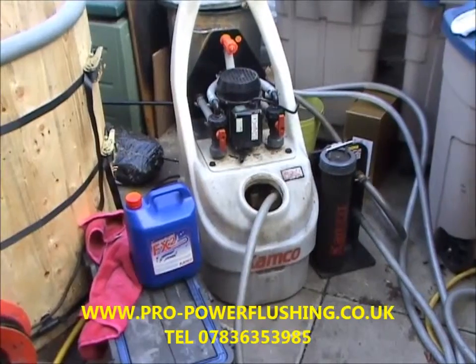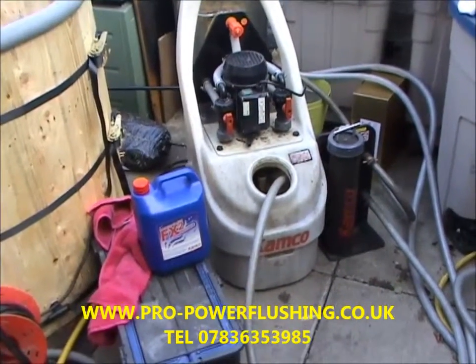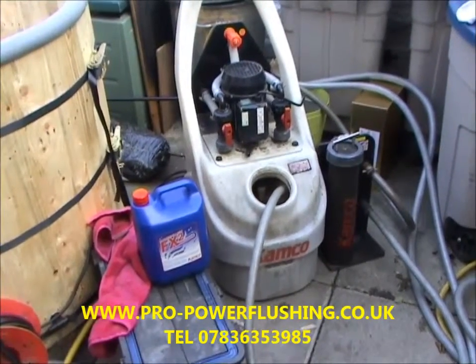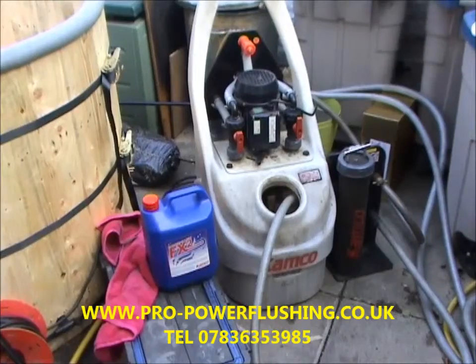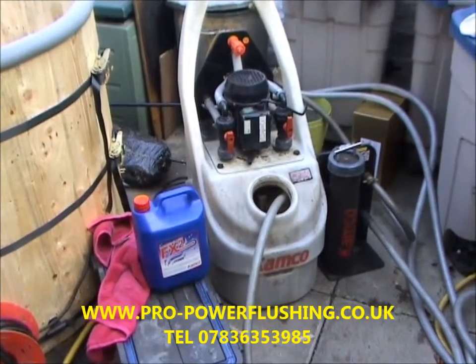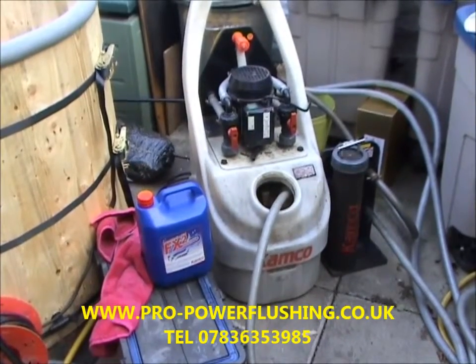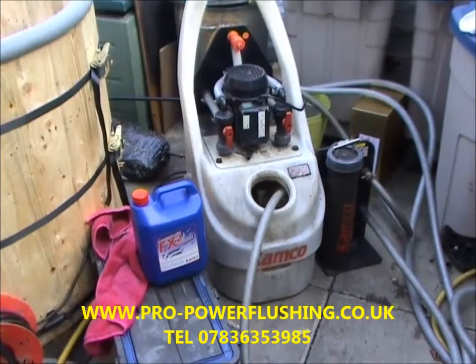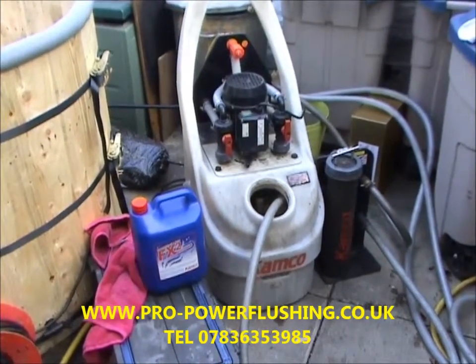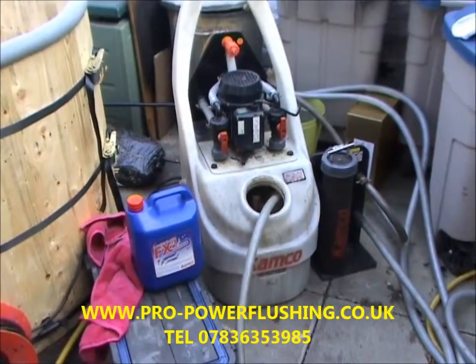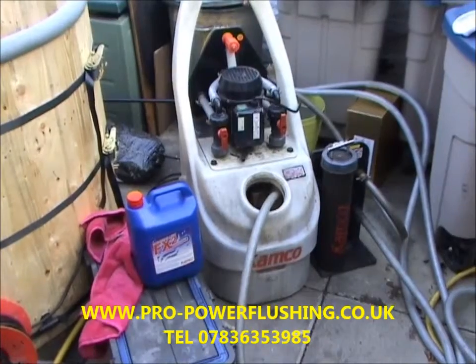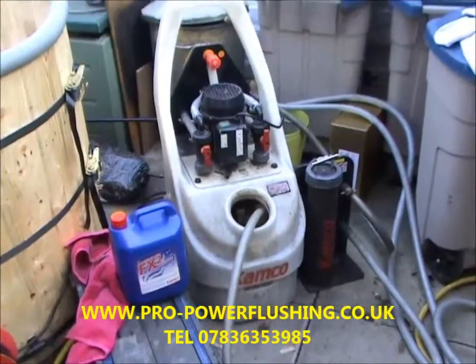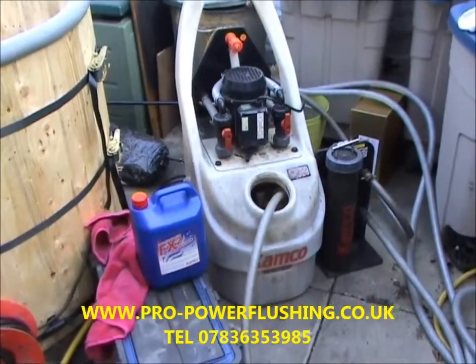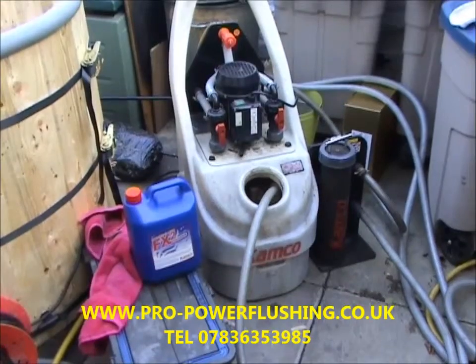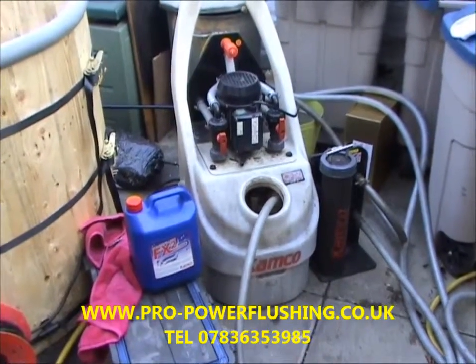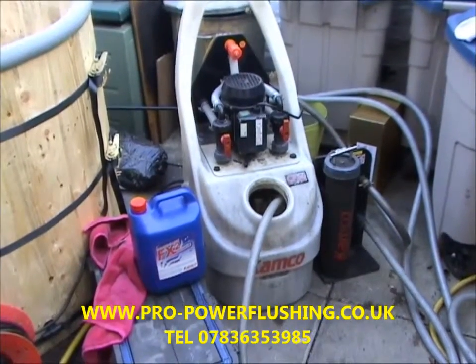We've done a system a few weeks back, and the system needed a power flush. It was a Worcester Bosch boiler, and the heat exchanger had cracked, and I think it was British Gas who were covering the system, but they basically said it needs a power flush before we're going to put a new heat exchanger in. So we went and power flushed the system, and that aluminium heat exchanger had actually cracked because of the rust and corrosion inside the central heating system, and that's why it's so important to get a power flush. We'll show you the metal on this magnet later. We know it will be heavy, and that metal running through your pump, diverter valve, plate heat exchanger, etc., eventually, if you don't get it out, it's just going to wreck your boiler.